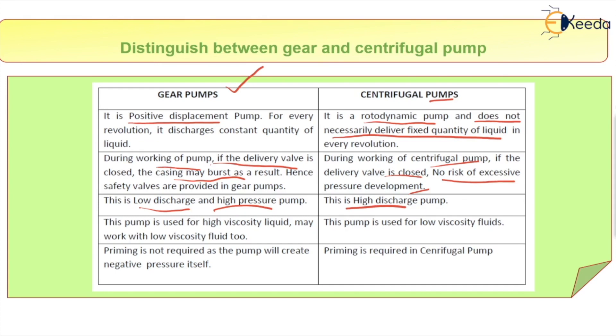In the case of a gear pump, it is used for high viscosity liquids — it may also work for low viscosity, but its main purpose is for higher viscosity fluids. In the case of a centrifugal pump, it is used for low viscosity fluids only. Regarding priming: for a gear pump, priming is not required at all because it creates negative pressure itself. In the case of a centrifugal pump, priming is required.